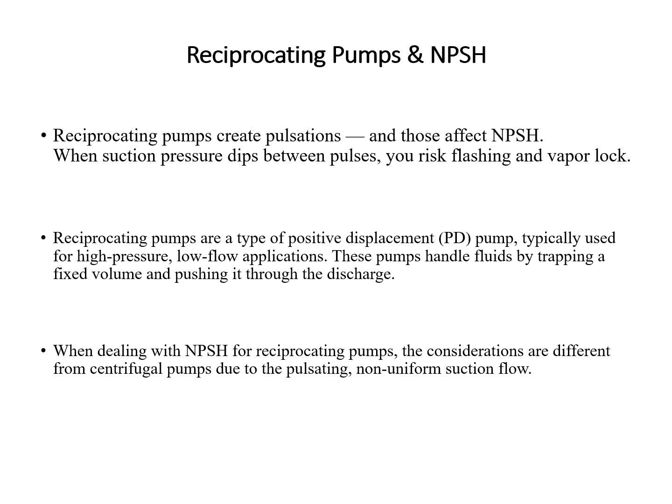Those pulses affect the net positive suction head. When suction pressure dips between pulses, of course, you will risk flashing and vapor lock. All this happens when the suction pressure goes very low. This will cause flashing. Flashing is a process of turning from liquid to vapor.